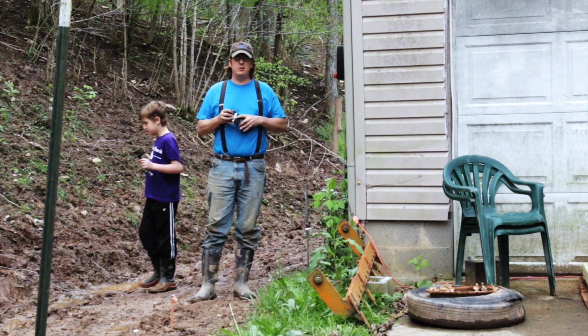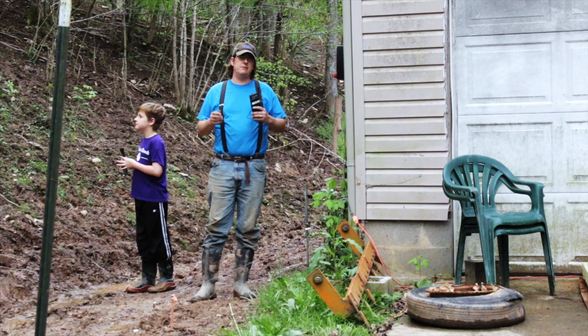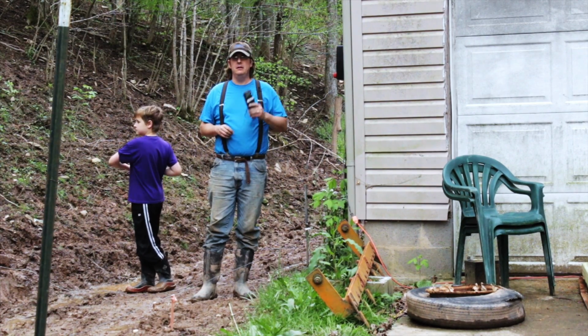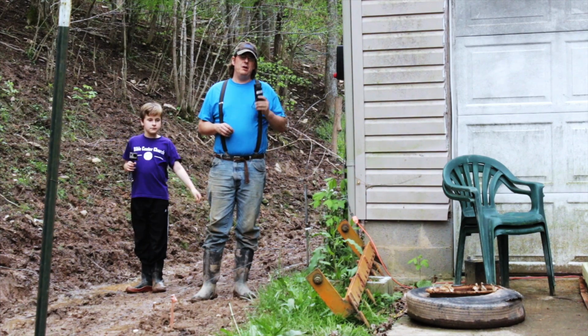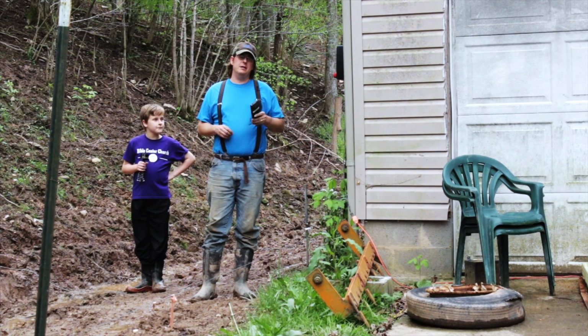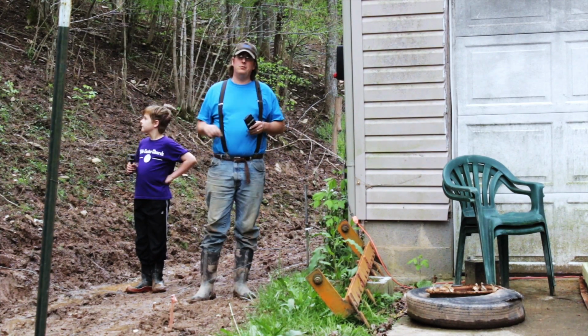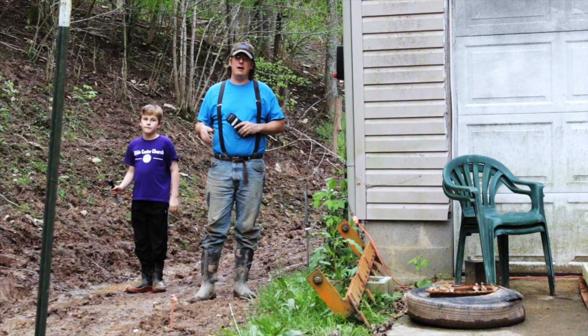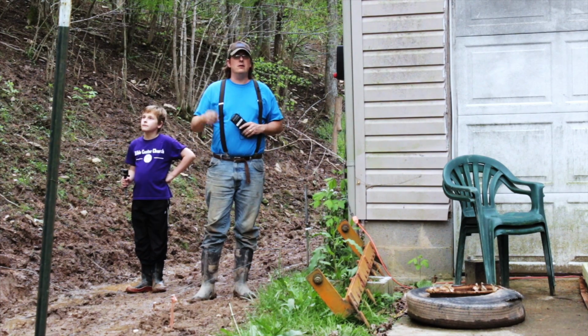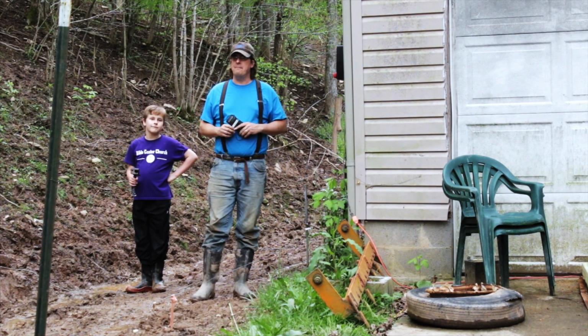So there's some other things I'm going to have to do, and maybe even research a little bit, make sure I'm not lying to myself. But right now, I know my grounds are really clean. I know I've got a good connection on those 3 ground rods. Those are 3 6-foot ground rods, so I've got a lot of ground field there. There's tons of water around here, so that's not an issue.